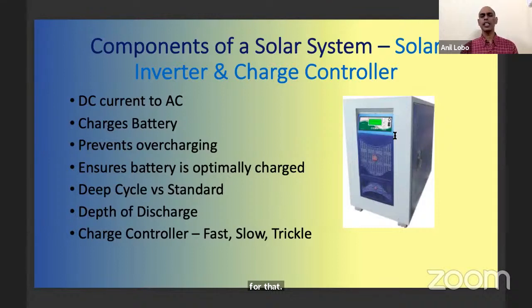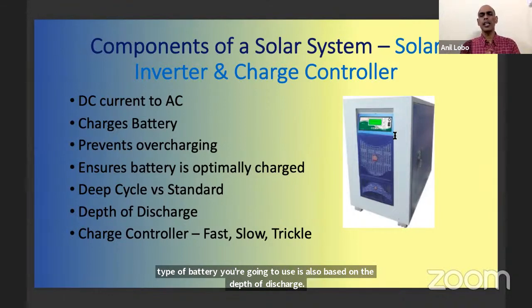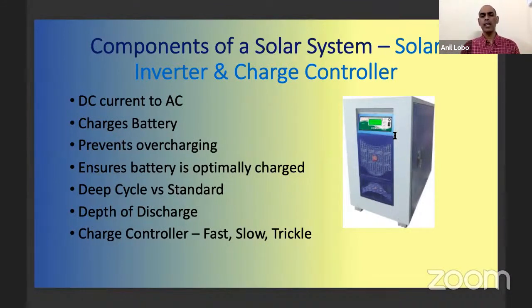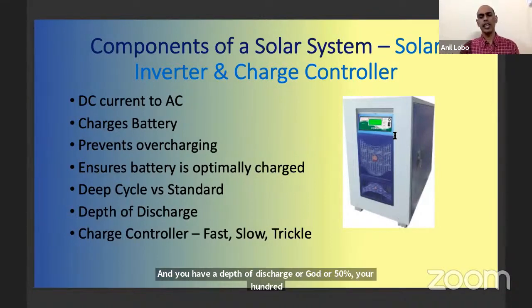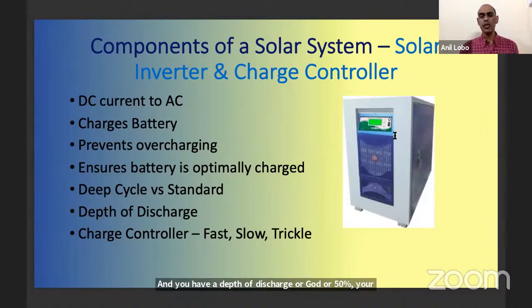And that brings us to the next topic. What type of battery you're going to use is also based on the depth of discharge. Lead acid batteries typically can discharge up to 50% of its capacity. So if you have a 100 amp hour battery and you have a depth of discharge, or a DOD, of 50%, your 100 amp hour battery is actually worth only 50 amp hours. So if you make your design calculation, it should be designed as a 50 amp hour battery, not a 100 amp hour battery. Whereas lithium batteries can be discharged almost up to 99.5%. I mean, theoretically, you can discharge 100%.